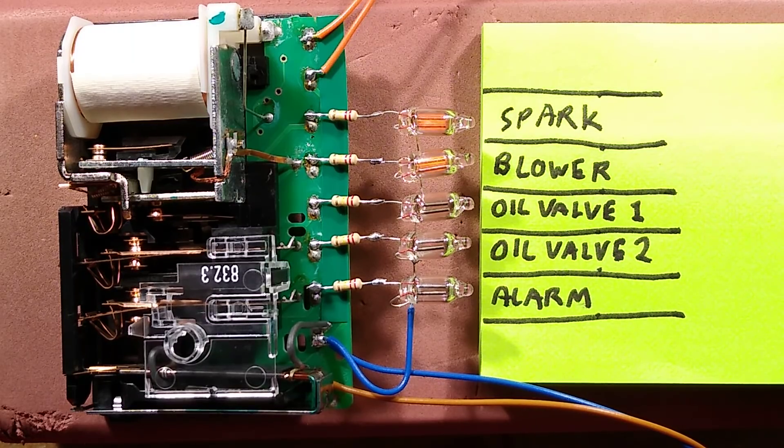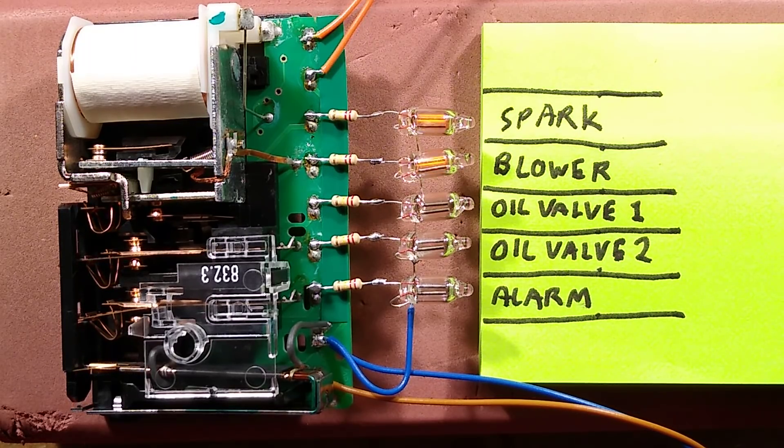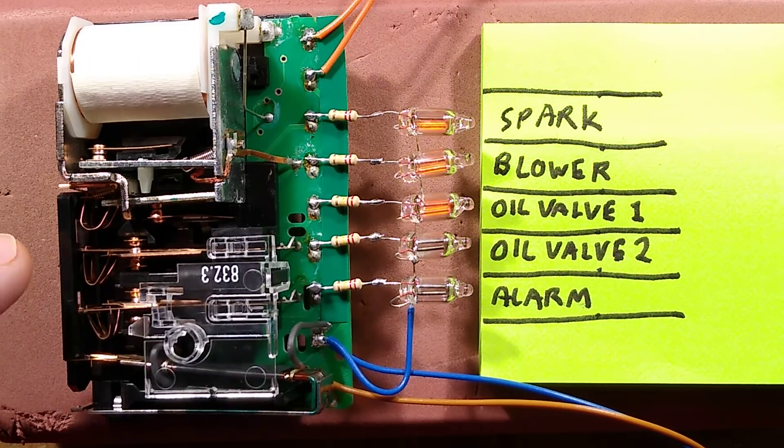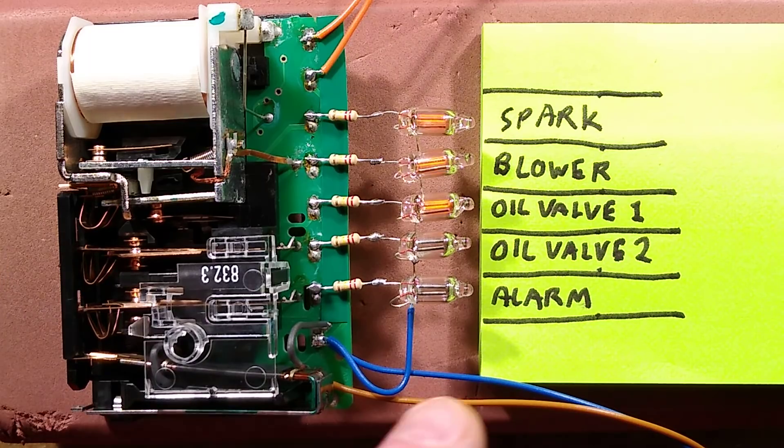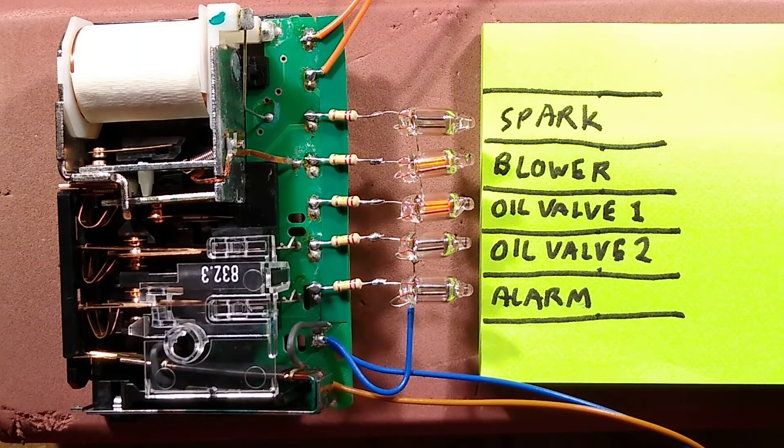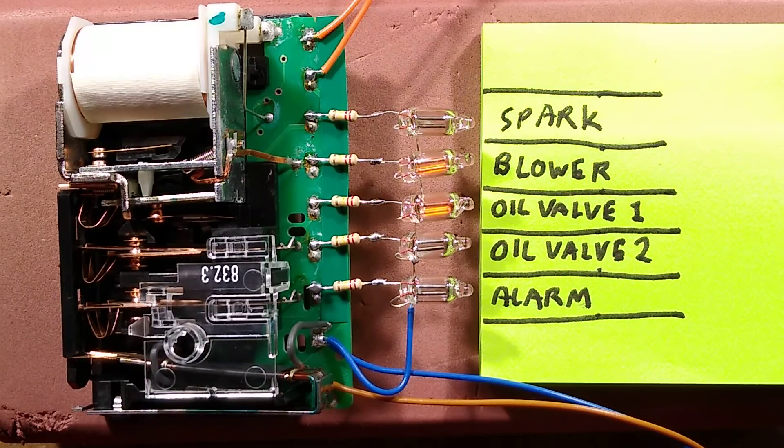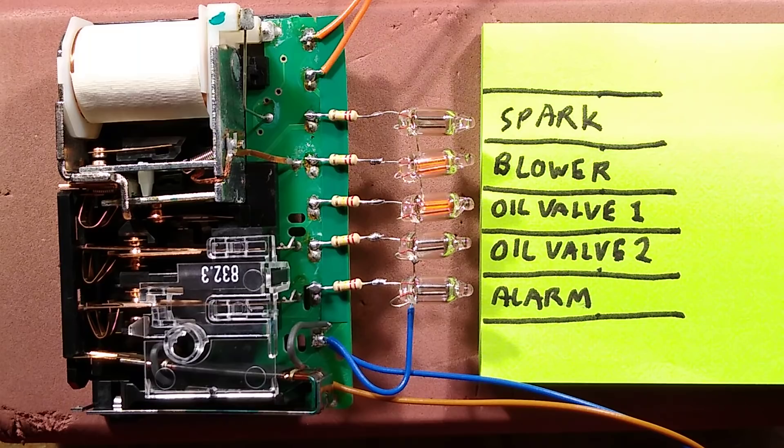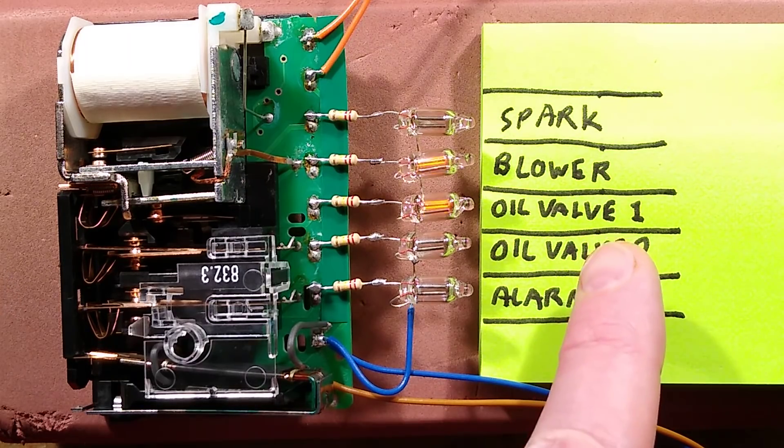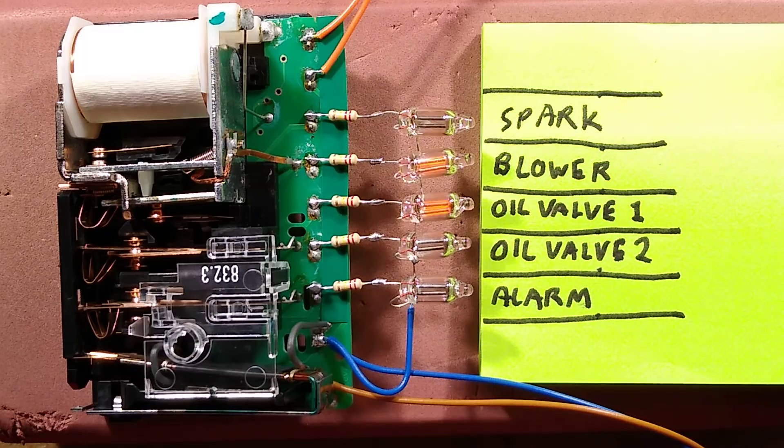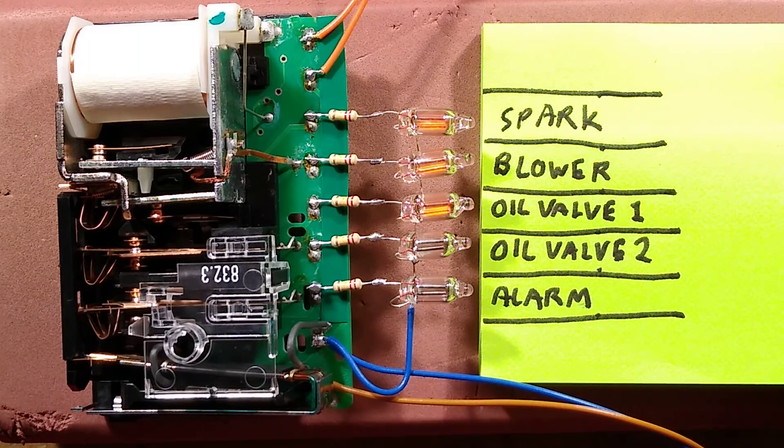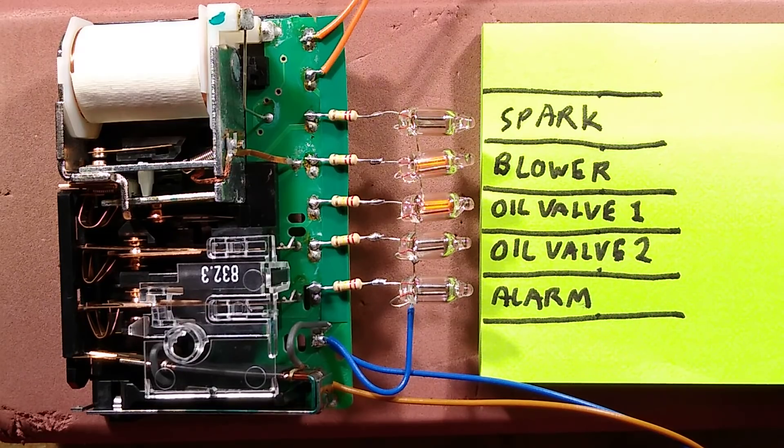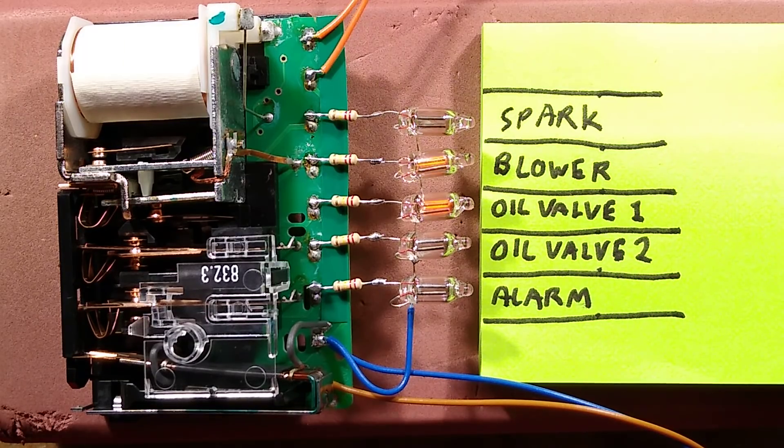So the first thing that happens is the blower is powered and the spark. The bimetallic strip is gradually moving across. You'll see this in greater detail later. It parks that contact. It's activated the oil valve one. I'm pushing the button. The magnetic, it's reached the end and released the magnetic trip. And now the system is resetting. It's cooling down and the blower and the oil valve are running. It's monitoring the flame. If I was to release this, it would start the spark again and it would try and restart the ignition sequence until it lit.